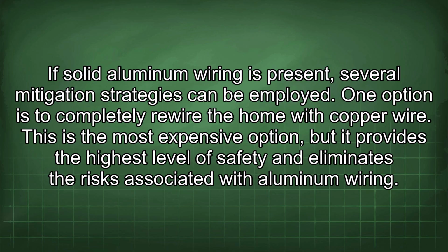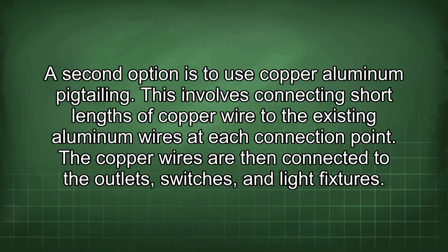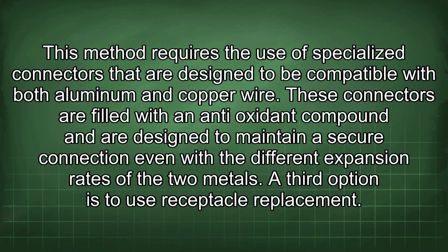If solid aluminum wiring is present, several mitigation strategies can be employed. One option is to completely rewire the home with copper wire. This is the most expensive option, but it provides the highest level of safety and eliminates the risks associated with aluminum wiring. A second option is to use copper-aluminum pigtailing. This involves connecting short lengths of copper wire to the existing aluminum wires at each connection point. The copper wires are then connected to the outlets, switches, and light fixtures. This method requires the use of specialized connectors that are designed to be compatible with both aluminum and copper wire. These connectors are filled with an antioxidant compound and are designed to maintain a secure connection even with the different expansion rates of the two metals.